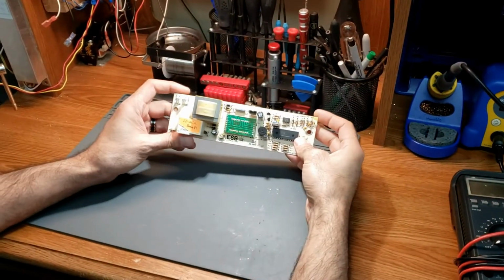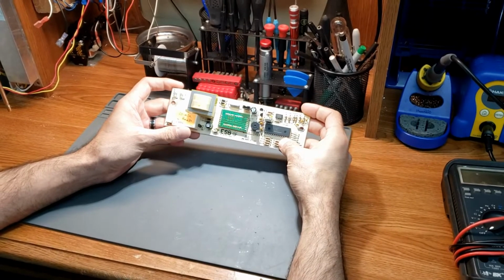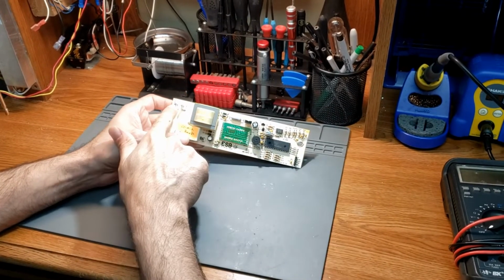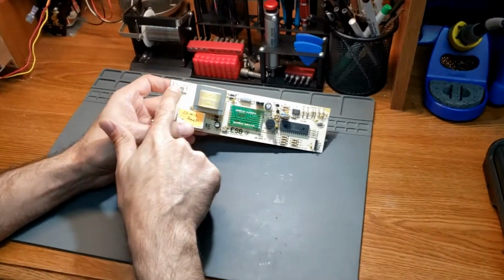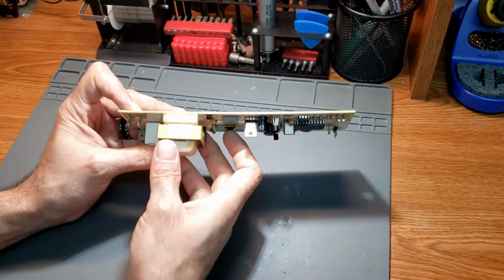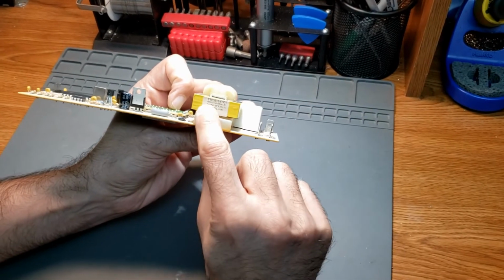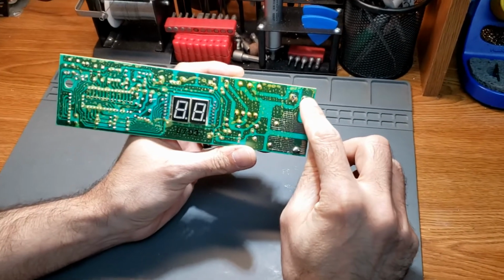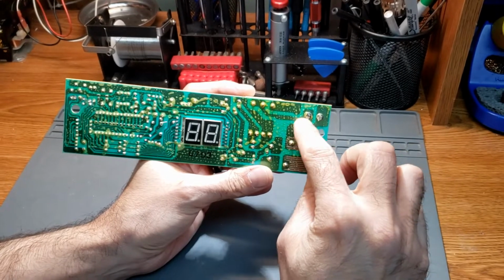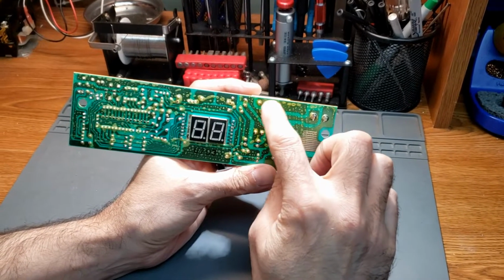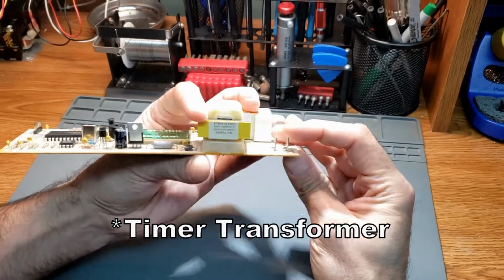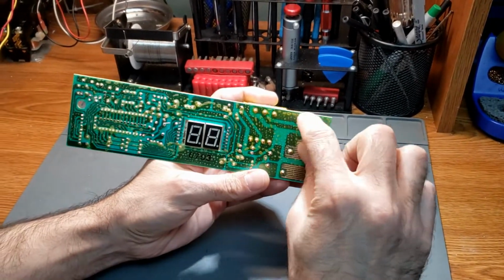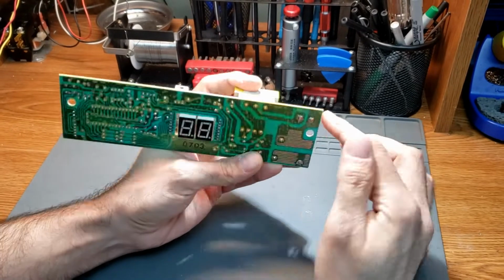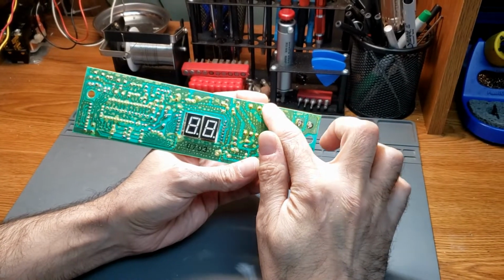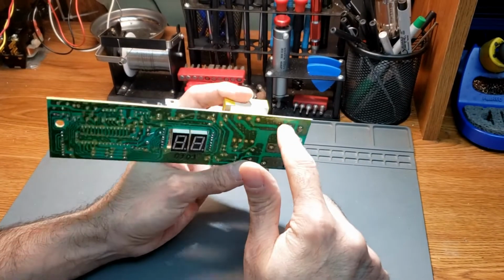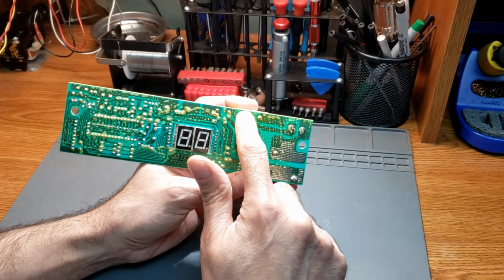This is a circuit board that needs repair. Right here is your input terminals, so that's where you have 120 volts coming in. The way the circuit is wired, this is a 120 volt transformer, and these are the two primary terminals. The first thing they're doing is providing power into the timer here. There's a fusible trace where it comes off of this terminal and goes to one leg of the transformer, and then this one goes to these two legs of the transformer.